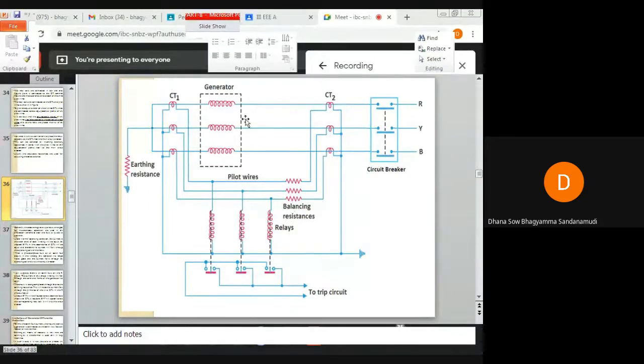So here, what we have seen is that this is our one phase winding, the R phase winding. The current entering this winding and the current leaving this winding should be the same. That is what is measured by the CTs of this phase R. If the current entering and leaving are not the same, then the differential current will flow through this relay and this relay will operate. That's what we have discussed.